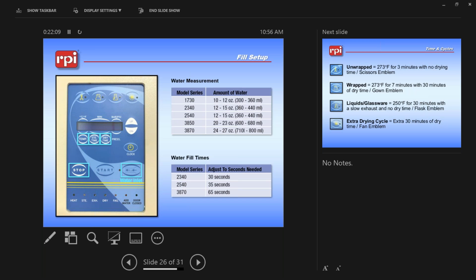Now, for units that have water pumps, what you'll do is you'll hit the stop key and what you'll see on the display is a code 102. You want to use the up key to go up to code 105. Once you get to code 105, you hit stop, and that will ask you for fill time. You can adjust it using the up and down keys to the size of unit, which, located in the bottom right, will be the time that you need to set for each size of unit. Once you've got it to the time limit that you need, then you'll be hitting the stop key again. And that should set your water fill for machines with water pumps.